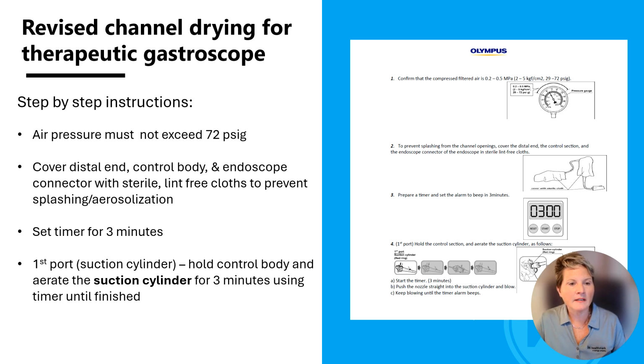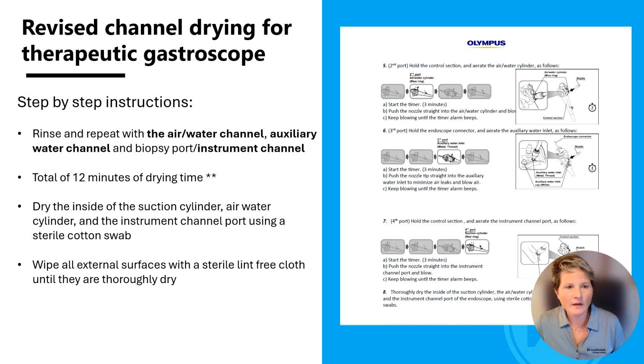drying machine. Then you set the timer for 3 minutes, and you go to your suction cylinder port, and you hold the control body with your hand and then aerate the suction cylinder for 3 minutes using the timer until it's finished. And then after that, you basically do the same thing over and over again with the air water channel, the auxiliary water channel, and the biopsy port or the instrument channel. So like I said, each one of those things you go through for 3 minutes, and that equals out to a total of 12 minutes of drying time.